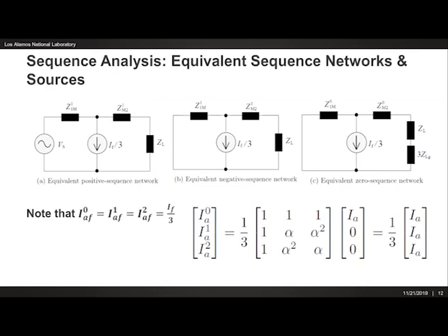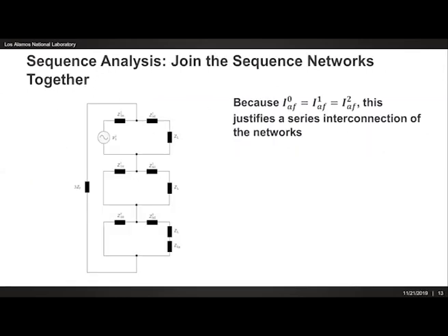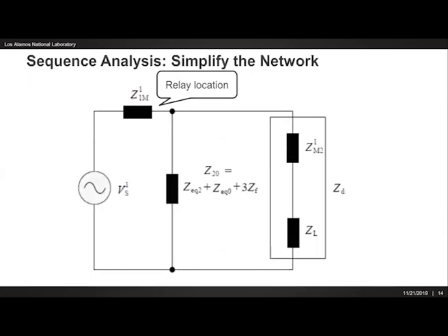If I break up the three-phase circuit into its equivalent sequence networks, and then I use the inverse sequence transform, what I see is the sequence component of the fault current, they're all equal. And this gives me an interconnection of the sequence networks where they're all in series. Doing a little bit of simplification, I got a Thevenin equivalent circuit, and I'm able to calculate what the current is measured by my relay.